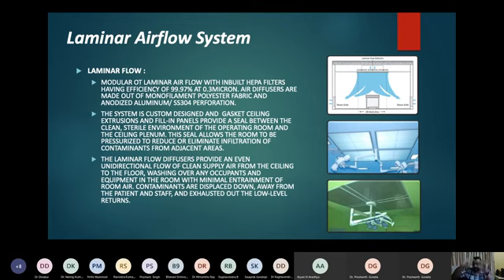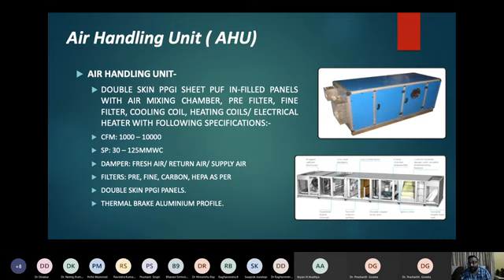This is part of the AC designing system, which comes as part of the modular operation theater. It comes to the air handling system. This air handling system is connected to the laminar flow, and it is called the AHU as well. As per NABH norms, each modular OT should have a separate air handling unit. You cannot use a centralized AC for each and every OT.